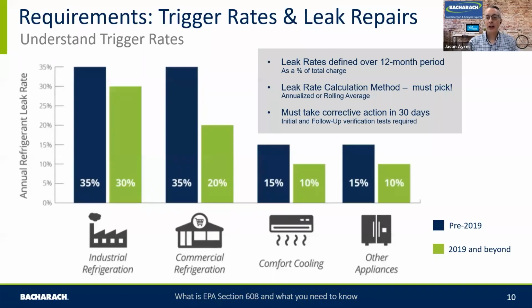Okay, so the trigger rates that are applied are at the asset level. If you've got 5 racks on site and they've got 100 pounds on it, you don't add them all together. The trigger rates that are applied are at the asset level. So there's no adding of these together to get your overall refrigerant consumption. These are done on the asset level. Think of it that way: every piece of equipment that has refrigerant in it falls under this trigger rate calculation. That could be a rack with all the connected features together, which is deemed as one system. You might have a chiller over here that's deemed as one system, but you don't add those numbers together to give your collective entrained volume leakage rate. I hope that makes sense. Yep, that's clear.